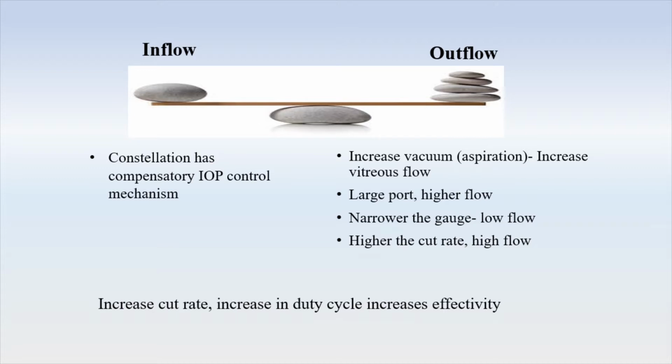Infusion system is no longer a concern in modern vitrectomy machines because they are automatically controlled. However, outflow is affected by factors like when we increase the vacuum, outflow increases; by larger port size, by high cut rate, and it decreases with the narrower gauge instruments.